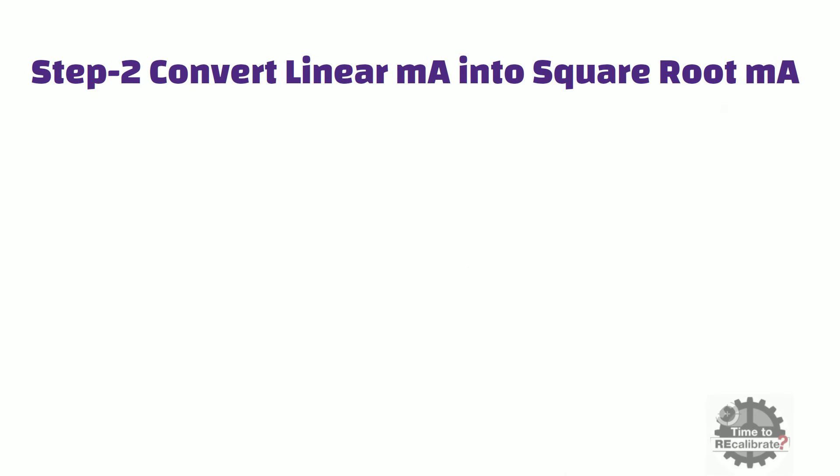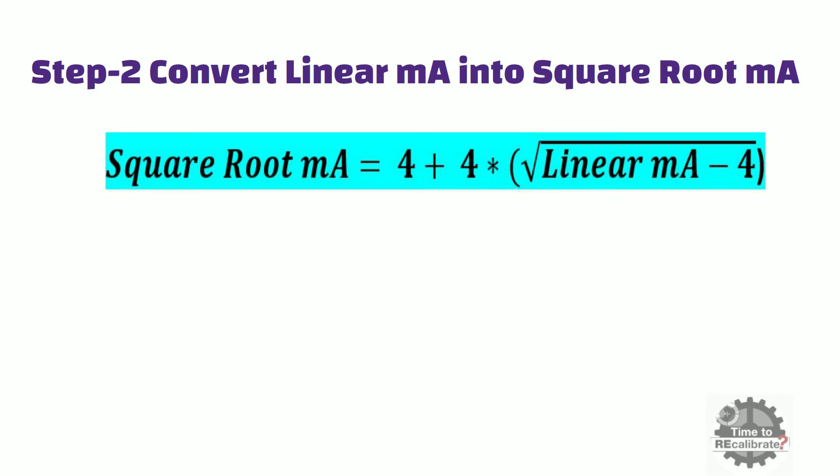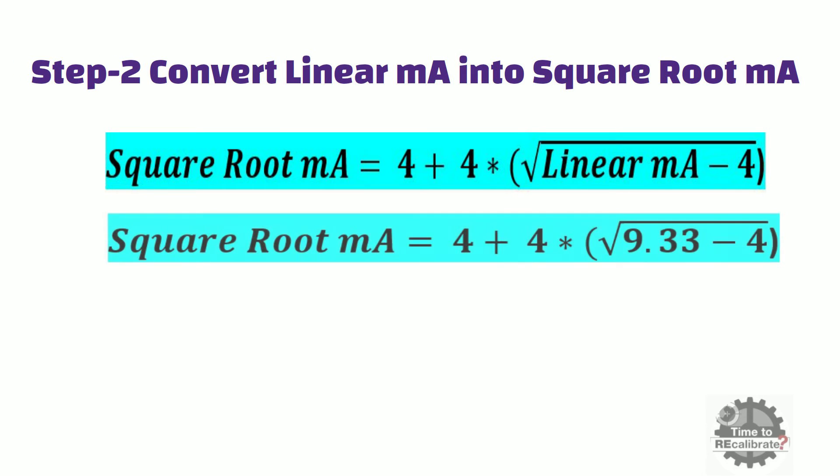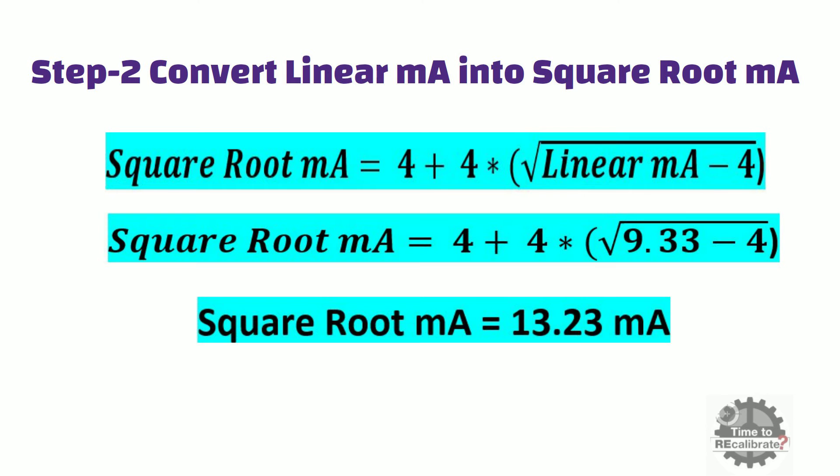Now in the second step, I am going to convert linear milliampere into square root milliampere. This is the standard equation for square root milliampere conversion, and we need to put the linear milliampere value in this equation. Then do the simple math calculation. You will get 13.23 milliampere.